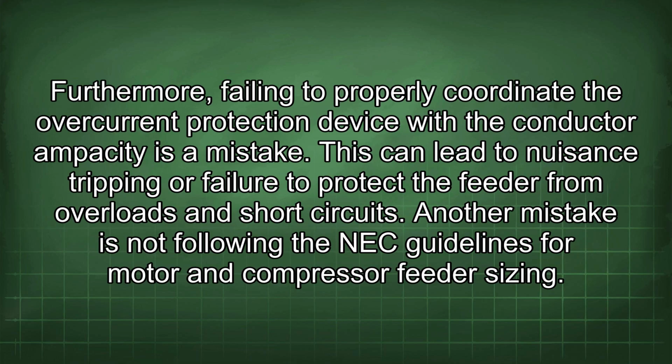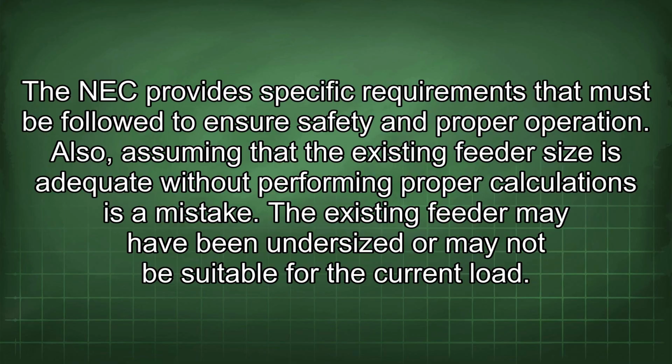Furthermore, failing to properly coordinate the overcurrent protection device with the conductor ampacity is a mistake. This can lead to nuisance tripping or failure to protect the feeder from overloads and short circuits. Another mistake is not following the NEC guidelines for motor and compressor feeder sizing. The NEC provides specific requirements that must be followed to ensure safety and proper operation.